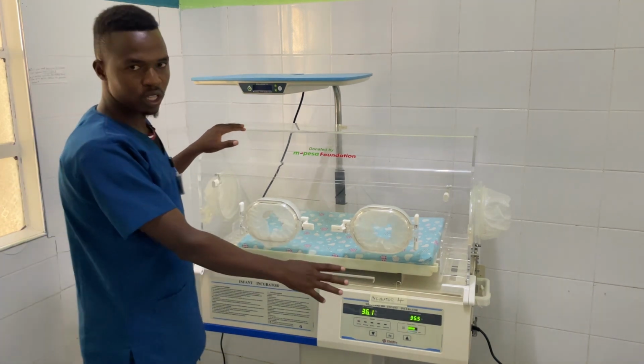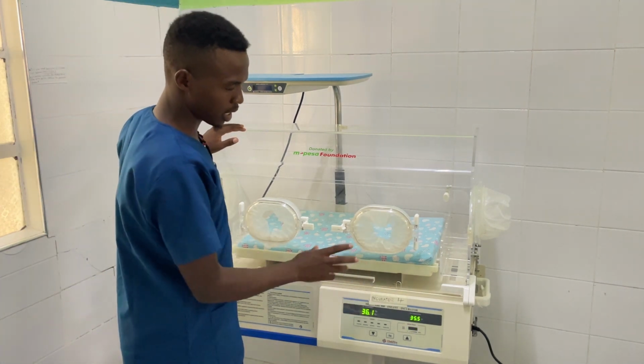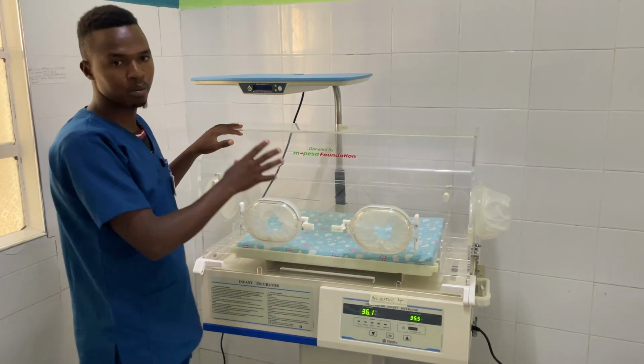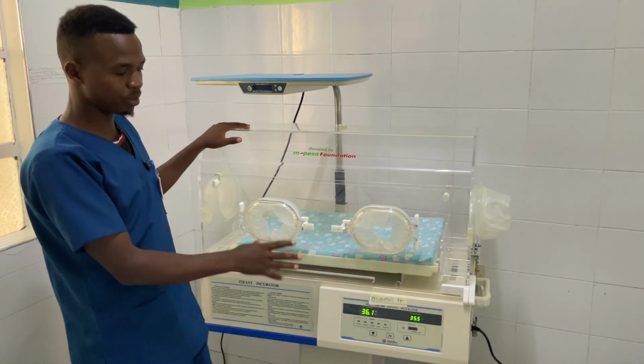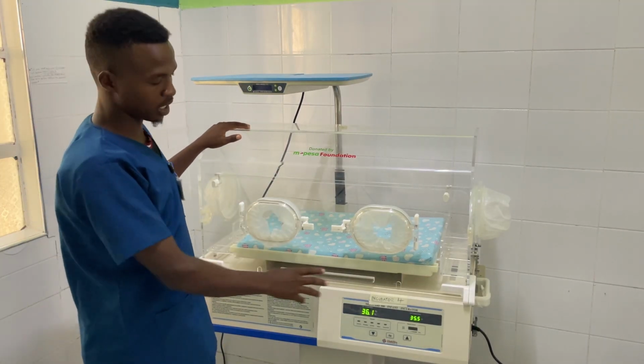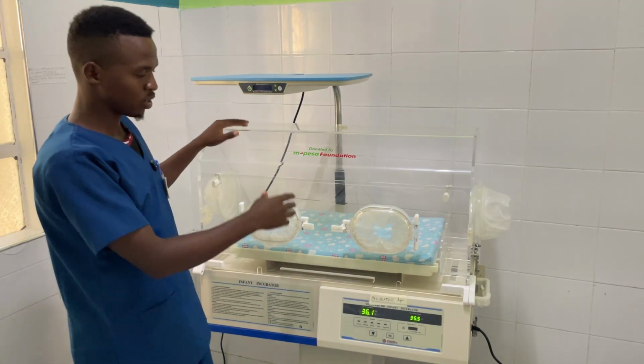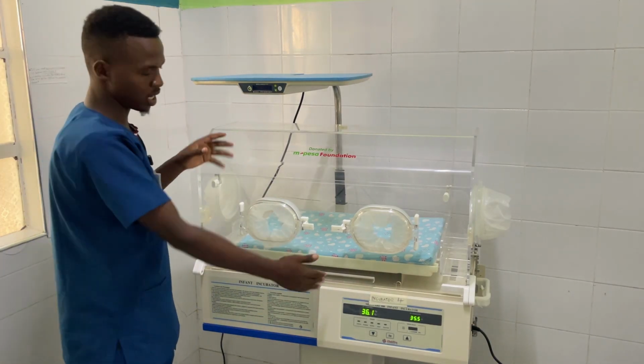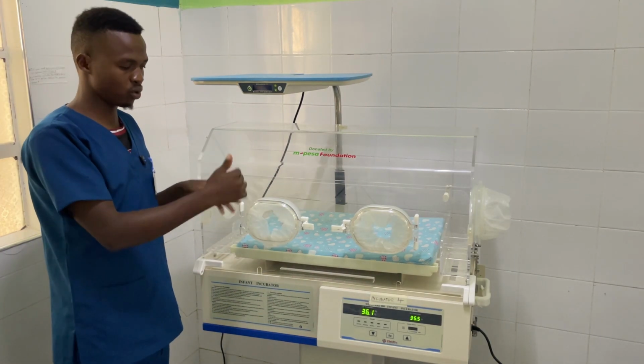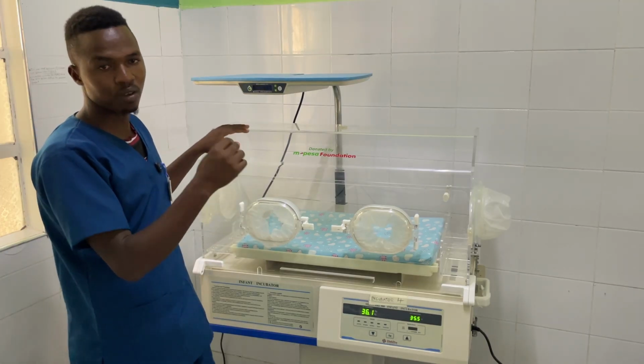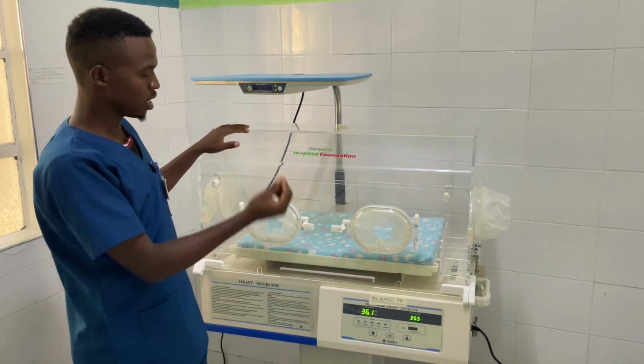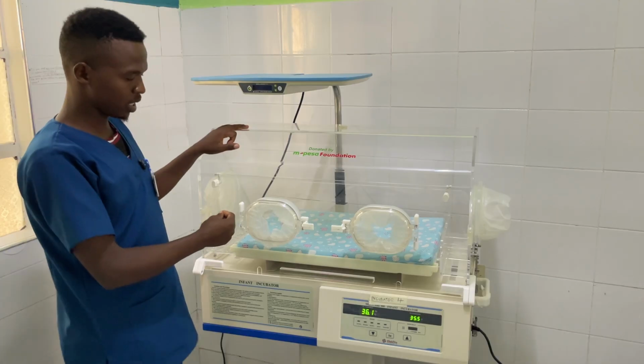Remember, although these are all external temperatures being recorded, you have to check the baby's temperature inside, because sometimes the machine could have a fault that gives a false reading. So you have to confirm that what is displayed here is what the baby's temperature is. That's why we also have thermometers. We use thermometers to check the actual baby's temperature.